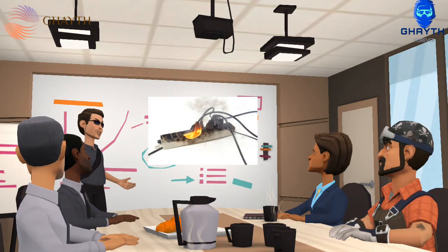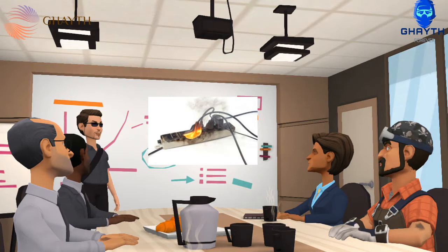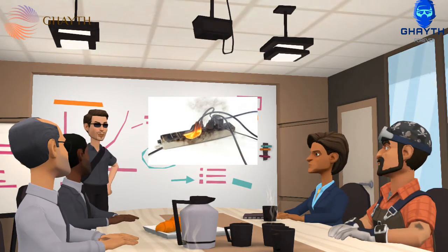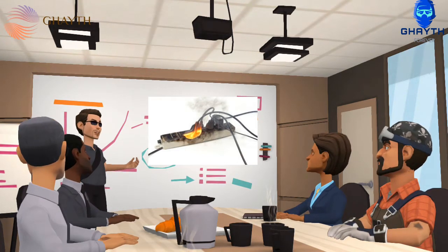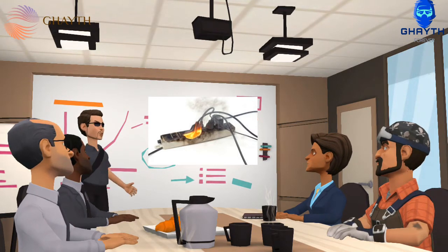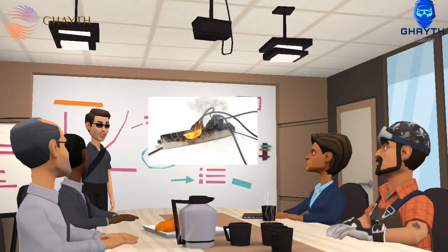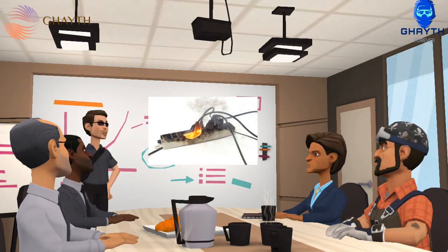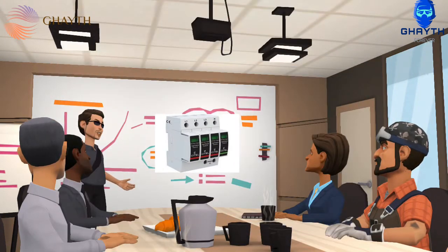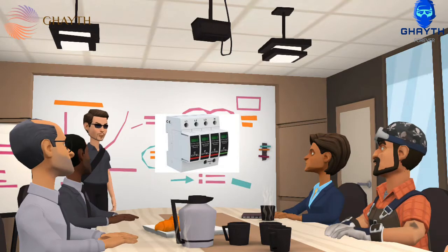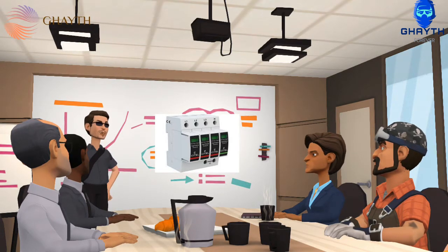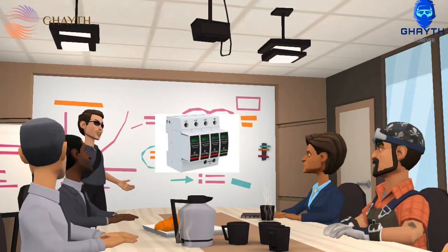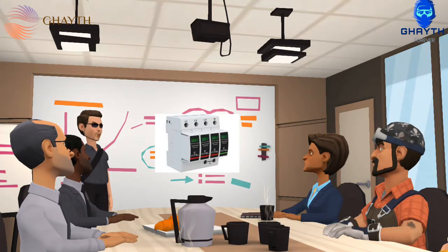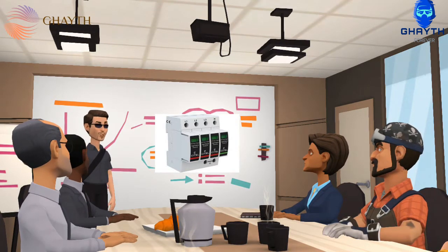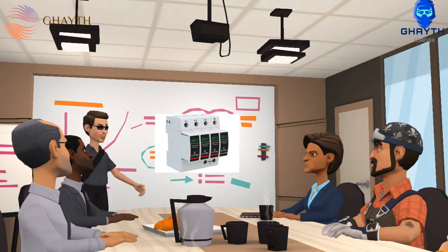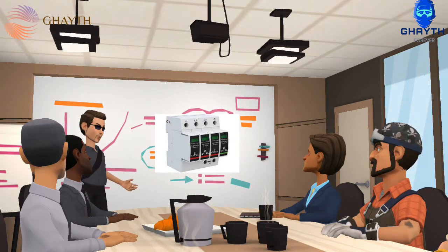Blocking is done by using inductors, which inhibit the sudden change in current. Shorting is done by spark gaps, discharge tubes, zener-type semiconductors, and metal-oxide varistors (MOVs), all of which begin to conduct current once a certain voltage threshold is reached, or by capacitors, which inhibit the sudden change in voltage. Some surge protectors use multiple elements. The most common and effective way is the shorting method, in which the electrical lines are temporarily shorted together, as by a spark gap, or clamped to a target voltage, as by a MOV, resulting in a large current flow.